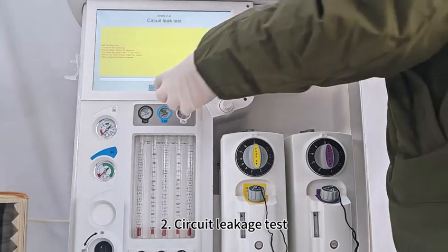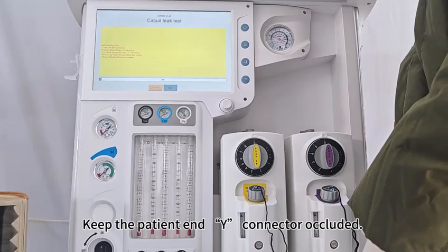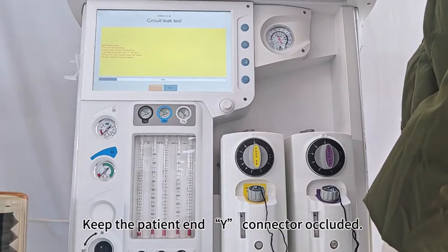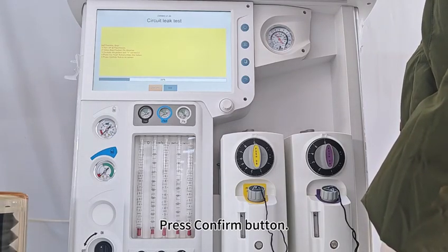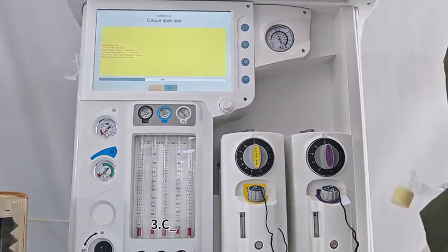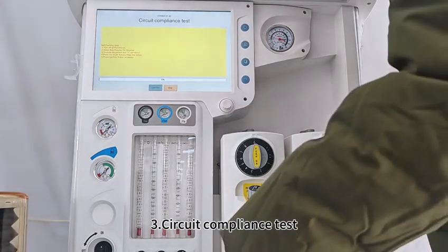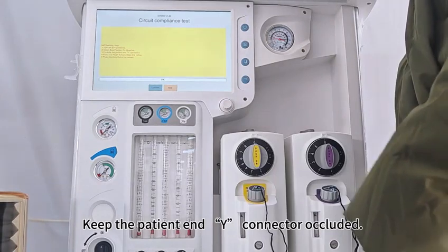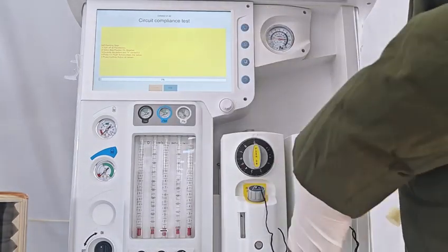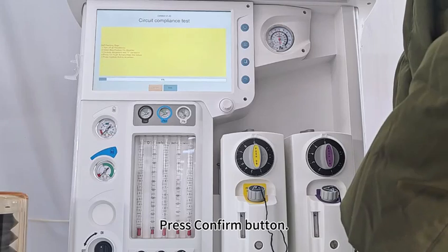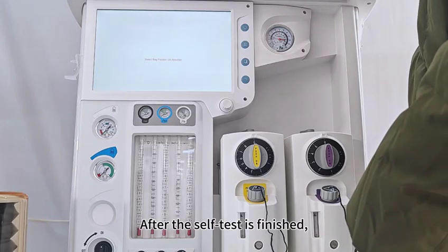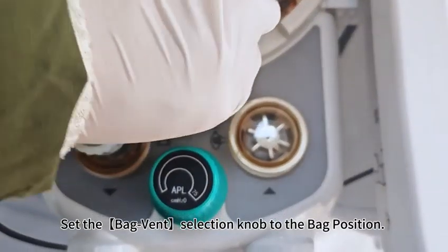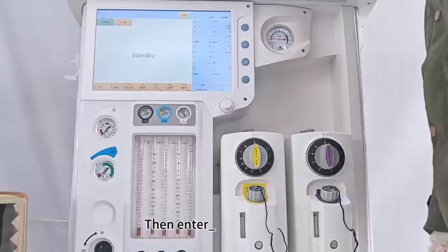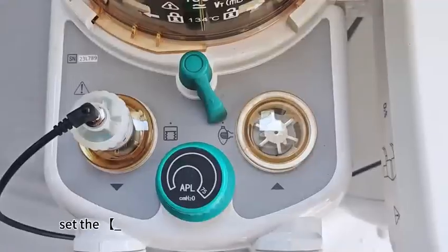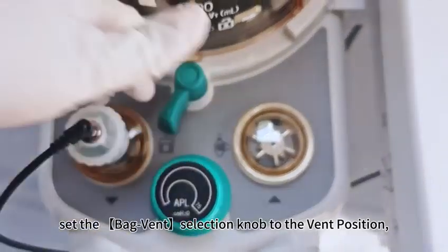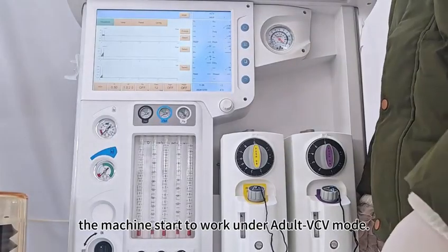Second, circuit leakage test. Keep the patient end "Y" connector occluded. Press confirm button. Third, circuit compliance test. Keep the patient end "Y" connector occluded. Press confirm button. After the self-test is finished, set the bag vent selection knob to the bag position. Then enter standby mode, set the bag vent selection knob to the vent position, the machine start to work under adult VCV mode.